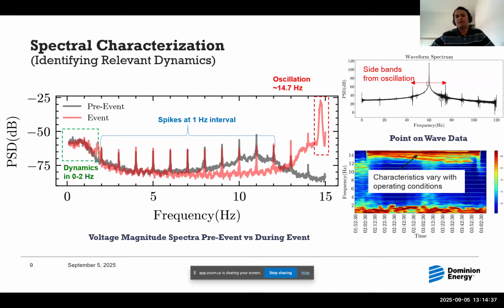Our waveform data triggers every time an event happens. In this case, it triggered as well. If you look at the spectrum, you'll see obviously the peak at 60 hertz, which is where our system is operating. But then you'll also see the symmetric side bands corresponding to the 14.7 hertz oscillation. So 60 plus minus 14.7, you can see those. That means the oscillation is indeed at 14.7 hertz. It's not at a different frequency.